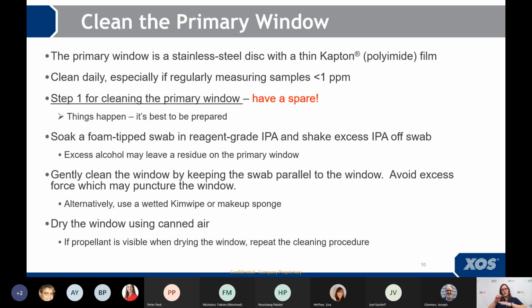If even this is making you nervous and you think maybe there's something else, you can use a wetted Kimwipe or a makeup sponge, and then you'd be even less likely to break the window. We do have some customers that do that. And then lastly, after you're done cleaning, you dry the window with canned air. When you're using the canned air, if you get some propellant that's visible when you're drying the window, you need to repeat the cleaning procedure.